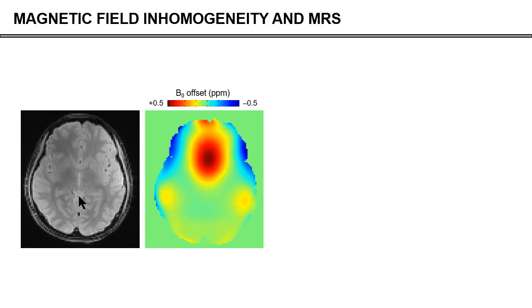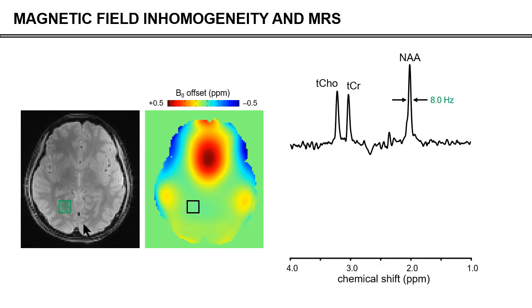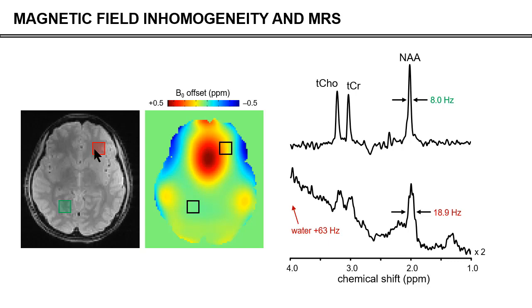Now, what kind of effect do these inhomogeneities have? Let's first look at spectroscopy. If we want to do spectroscopy of a volume that on the B0 map is quite homogeneous — nice and green — the spectrum is going to look nice, with narrow lines. If you now move the spectrum to a different location where B0 is a little higher and there is a gradient over the volume, that will lead to broadening of the resonance lines, and because of the elevated B0, the whole spectrum is shifted by 63 Hz in this case, leading to poor water suppression. So inhomogeneity is bad for spectroscopy: your resolution goes down, the water suppression gets worse.